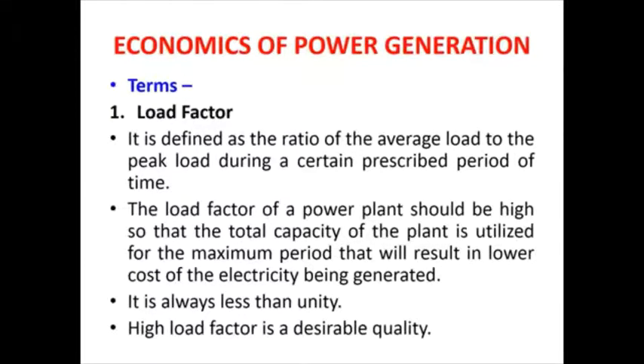The load factor of a power plant should be high so that the total capacity of the plant is utilized for the maximum period. That will result in lower cost of electricity being generated. What this sentence means is, if load factor is high, then the total capacity will be utilized. Suppose a power plant has a capacity of around 100 megawatts, and out of the 100 megawatts, 90 megawatts is utilized, then the load factor becomes 0.9. So from the maximum capacity around 0.9 is utilized, and we can say that the load factor is higher. So it is always less than unity, and high load factor is a desirable quality.